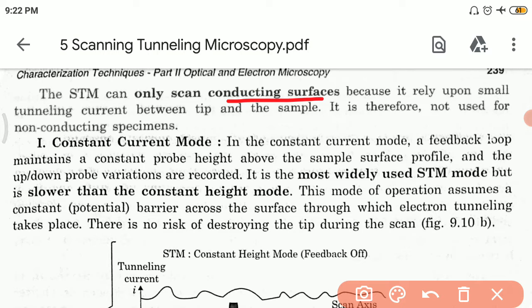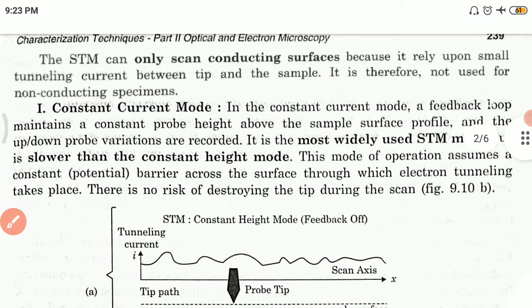Surfaces which are electrically conducting, because it relies upon the small tunneling current arising between the tip and the sample. Therefore, in other words, it cannot be used for a non-conducting specimen or sample. Now let us discuss the two modes of operation of the STM.